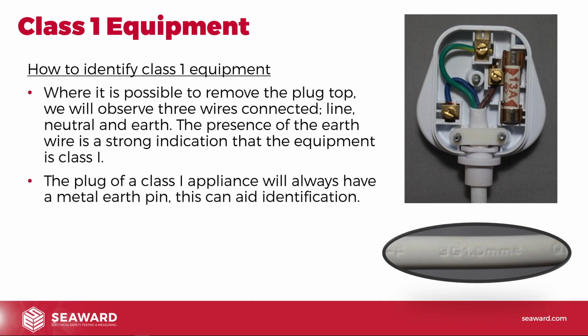The plug of Class 1 appliances will always have a metal earth pin, and this can aid identification. So if you see on the plug from the outside that we've got a plastic earth pin, that's generally telling you they're not expecting any continuity through that. It's just there to operate the shutters on the socket when you put the pins in and things like that. So if it's Class 1 equipment, there will be a solid earth pin. One thing to watch out for on counterfeit equipment, sometimes you will come across half-sleeved earth pins. So you've got an earth pin that's half metal and half plastic. That's totally dodgy, it's totally counterfeit, so if you do see those, please fail them straight away. They shouldn't be like that.